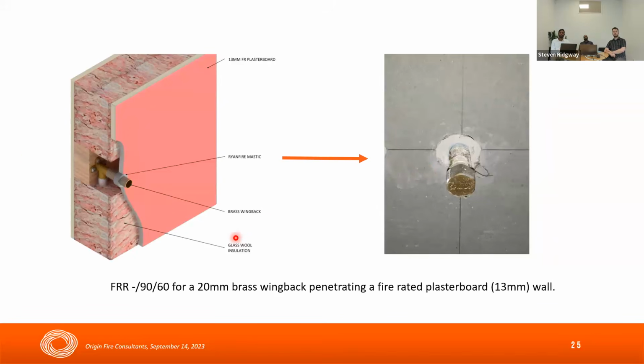So there's another fire stop system that I've shown here. This is a brass wingback that's penetrating a fire rated wall. This is for a water supply point just below the wash basin. The product is the fire sealant, but this whole thing is a system. So that's a fire rated plasterboard, and then the brass wingback that's penetrating that, and then the fire sealant that's going in the gap. All this is a complete system, and for a 20 mm brass wingback, the fire resistance rating is -90, 60. So this makes up one of the systems in a building.